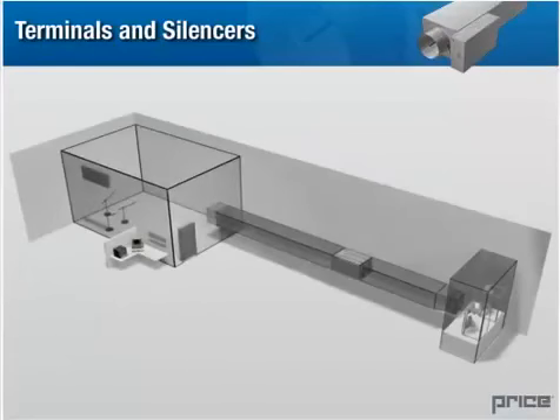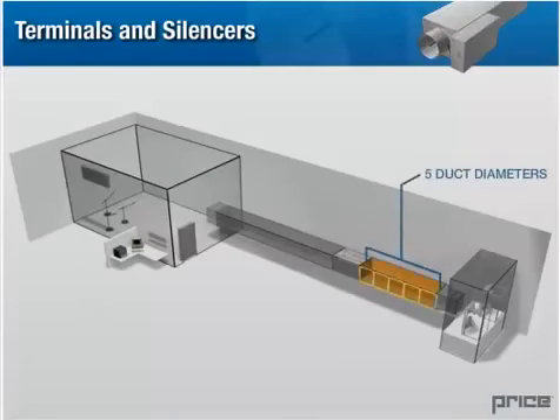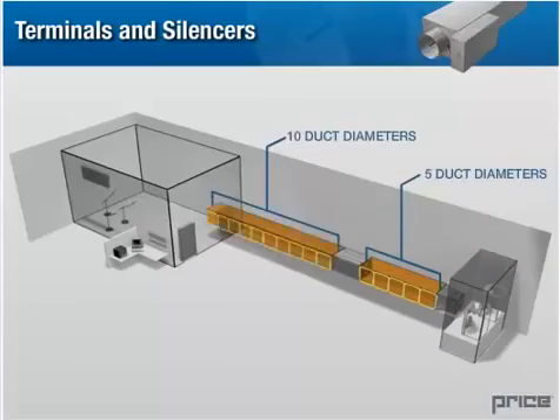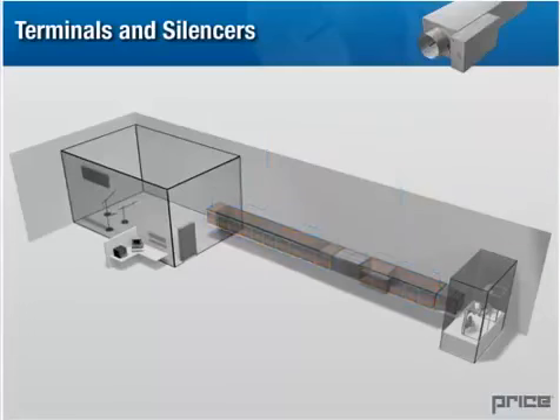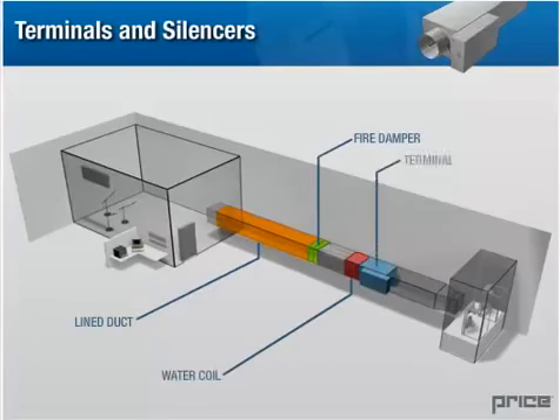Industry standard silencers are tested under ideal conditions with 5 equivalent straight duct diameters upstream and 10 straight duct diameters downstream. This testing procedure does not take into consideration the interaction a silencer has with other duct components. Correction factors for system effects and generated noise have been suggested, but the designers are often not aware of them, nor are these correction factors fully reliable.